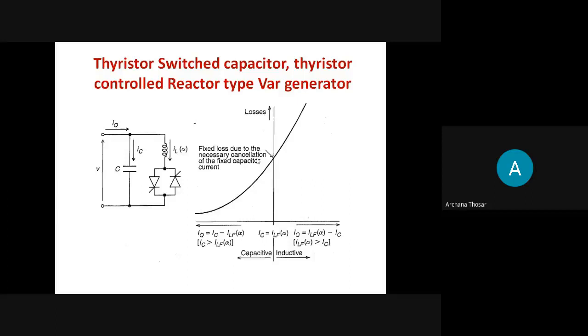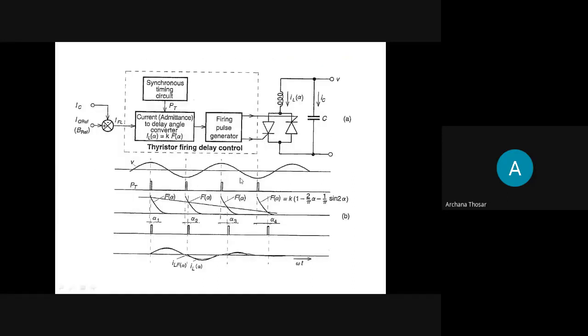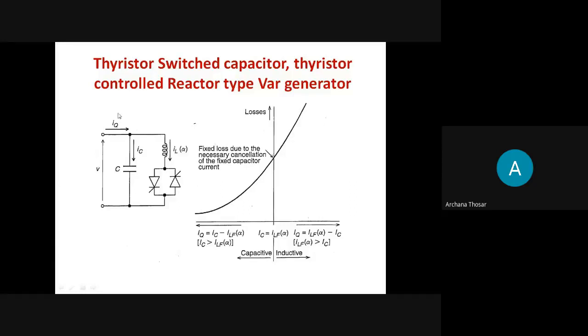So it is a little bit different, because here the capacitive and inductive part will be controlled by the triggering of these devices. This gives you the dynamic compensation of the power transfer system with the intention of minimizing losses, and it increases the operating flexibility because you can move this line and understand how much capacitive and how much inductive part is required to get the maximization of power transfer over the transmission line.